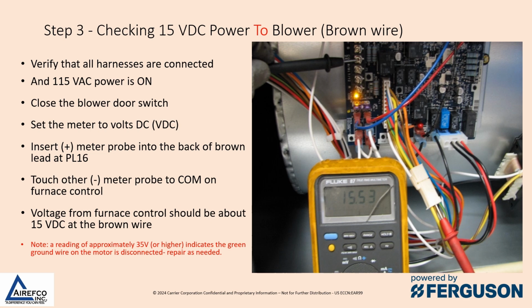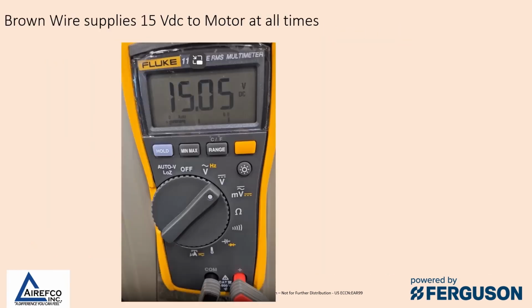Note, a reading of approximately 35 volts or higher will indicate the green ground wire on the motor is disconnected. Repair as needed. So when testing the brown wire, you should see 15 volts DC to the motor at all times when the furnace is powered.